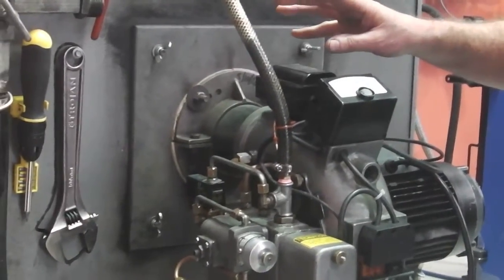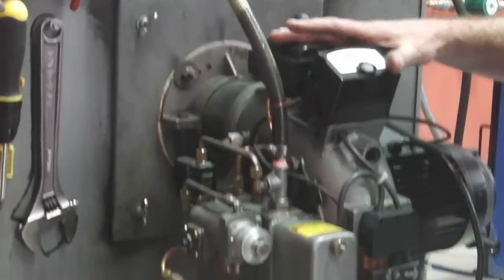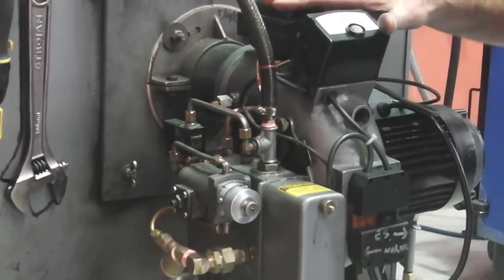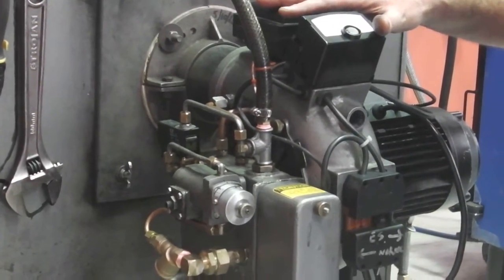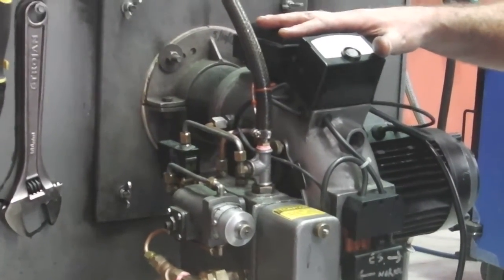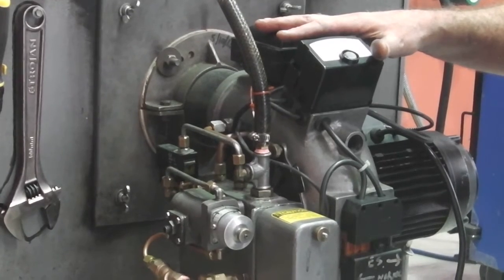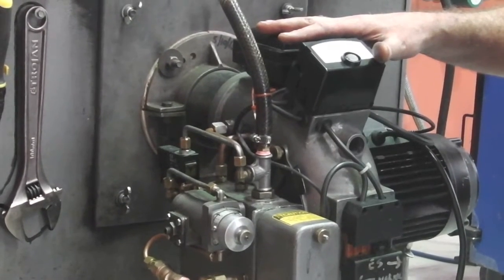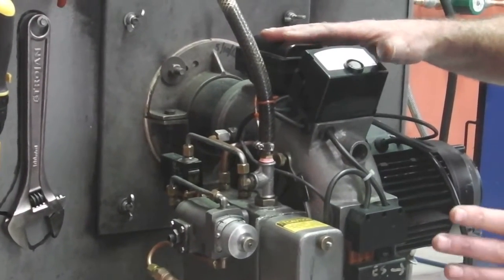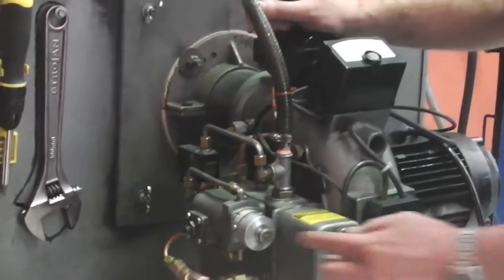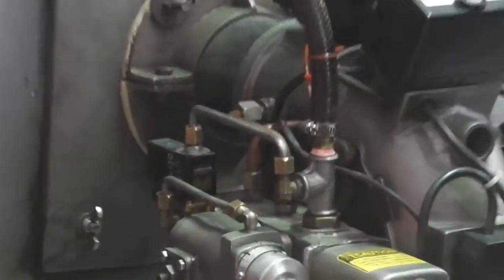The first thing is when these BR-10s arrive at a customer's site, we set them up for the correct flame length for the air furnace or the boiler that they're going to be fitted in. However, what is adjusted at the factory are two elements, the oil and the air.